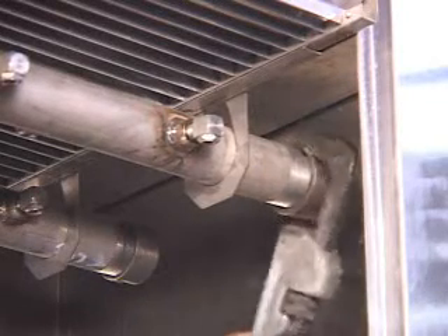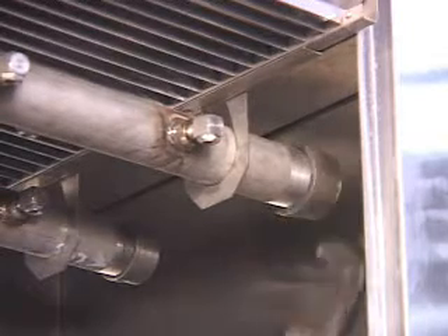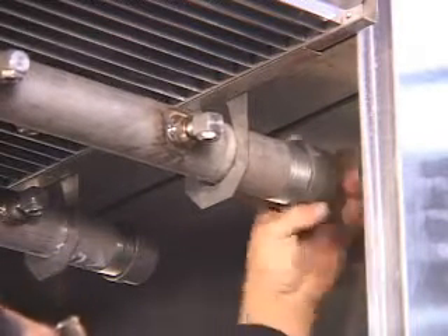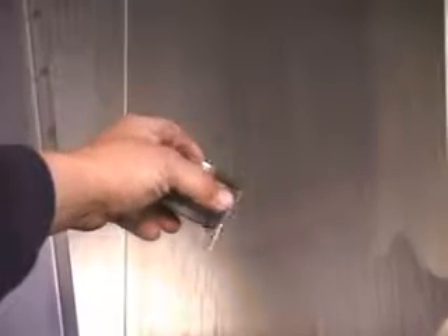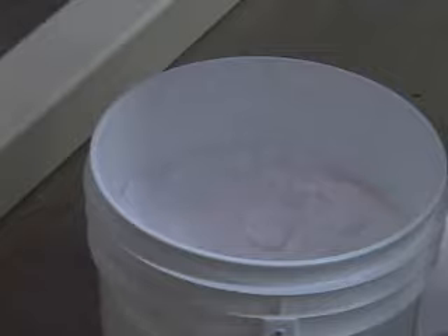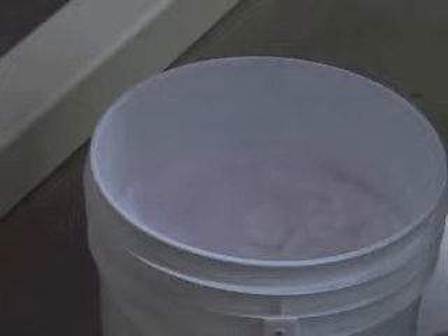There are stainless steel caps on the end of each water spray pipe. These can be removed and a pail can be used to catch contaminants inside the pipe while jogging the water pump. A powdered acid descaler is available from Samuel Jackson to help remove scale from the spray chamber. This is packaged in a 50-pound pail. We recommend using about 10 pounds of this placed directly into the spray chamber with fresh water.